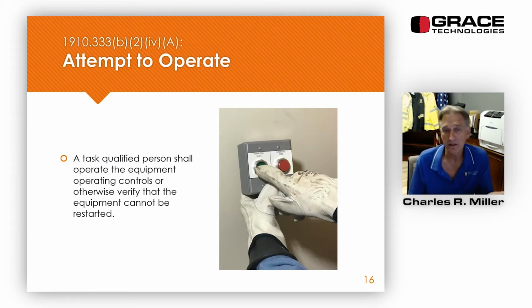So a task qualified person shall attempt to operate the equipment, operating controls, or otherwise verify the equipment cannot be restarted. I teach a lot of classroom seminars, and a lot of places want an additional half a day for hands-on training with their live equipment. With the hands-on training, we'll put a piece of equipment into an electrically safe work condition, or I'll have the qualified workers do it.